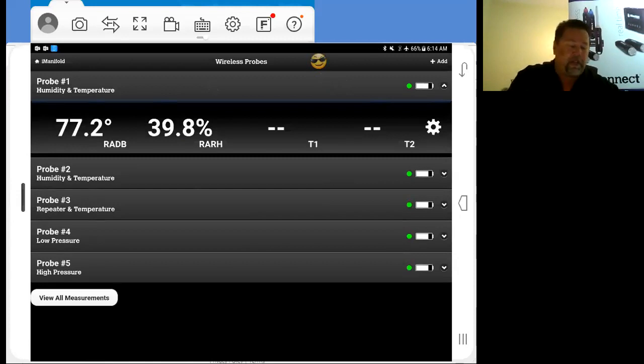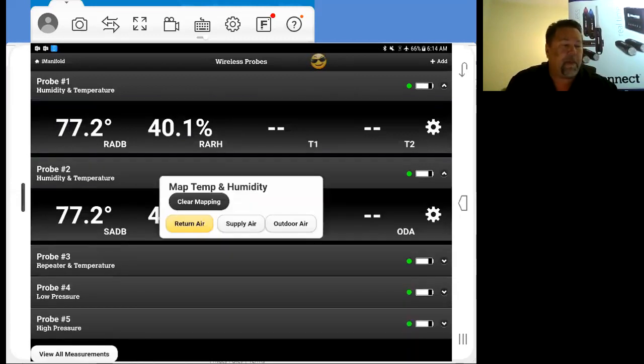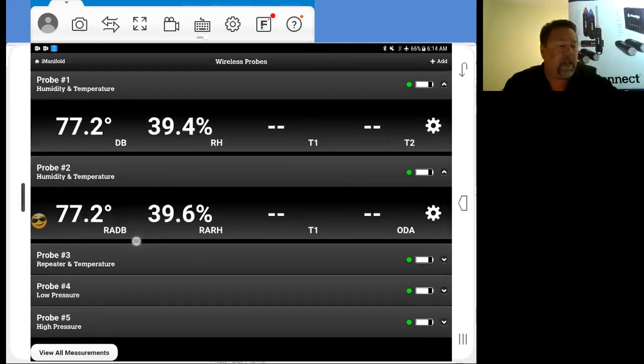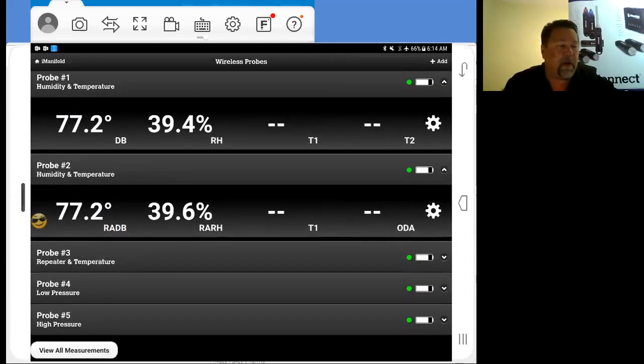Now, if I wanted to change this, it's a simple thing about just tapping the temperature, and then you can map it to supply, return, or outdoor air. Rather than going over there and pulling the probe out and saying, oh my gosh, I've got them reversed. It's a simple thing. Right here, here's our supply air. If I want to switch that, I can tap return air. And as you can see, I've got return air dry bulb now, but my probe number 1 skipped its mapping. So just always make sure, open up both of those, make sure you've got them in place. The 77.2 is my supply air. So now I've got my supply air and my return air mapped up.